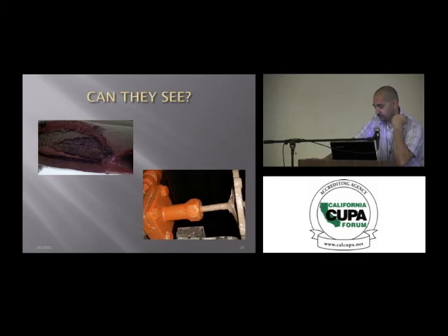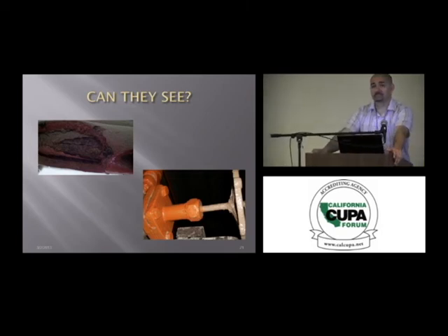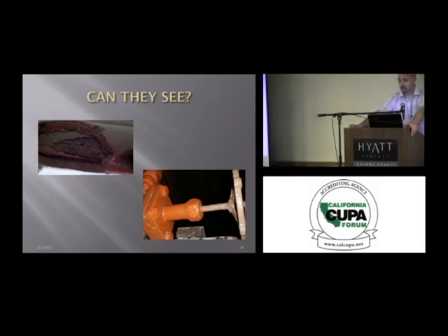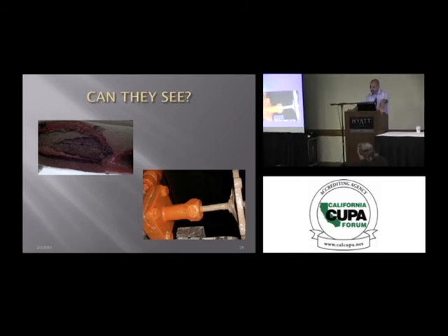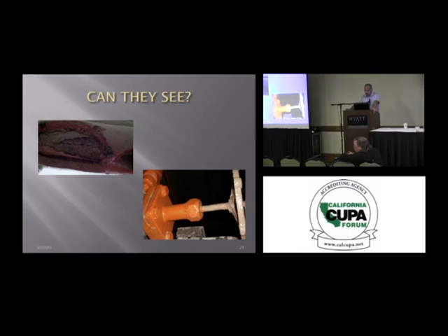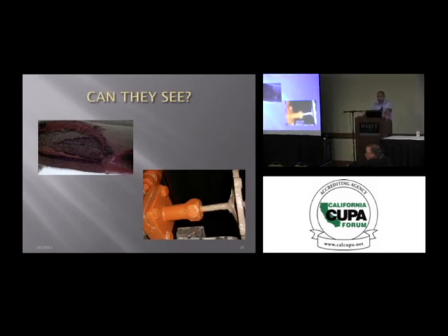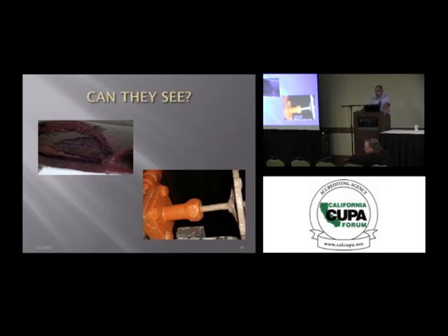I teach emergency response, and I'll tell you what, we've had a number of times when firemen have tried to turn a valve and they can't turn it. They need to backseat that valve, clean that stem up, loosen the packing nut, lube everything up, run it in, run it out. Now, IIAR says that we should be doing that twice a year. That is overkill. It's a financial burden on the facilities. The valves don't go bad in 6 months. Once every 3 years in non-corrosive areas is more than enough.